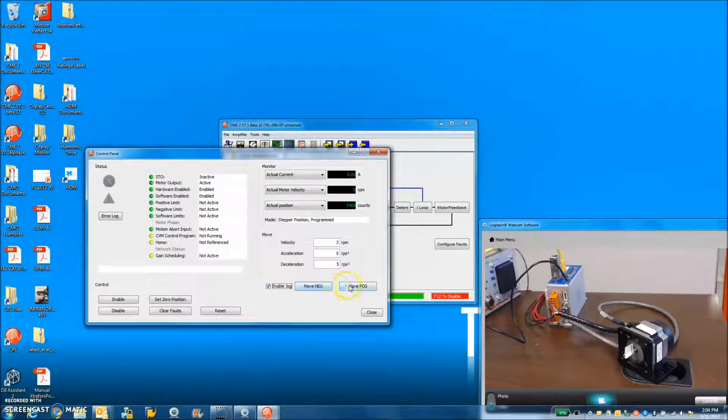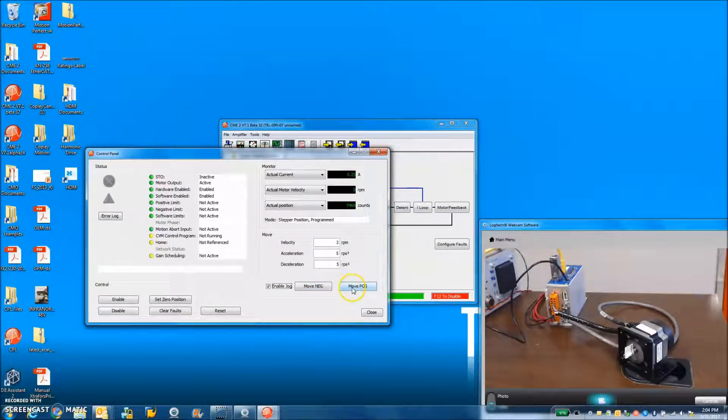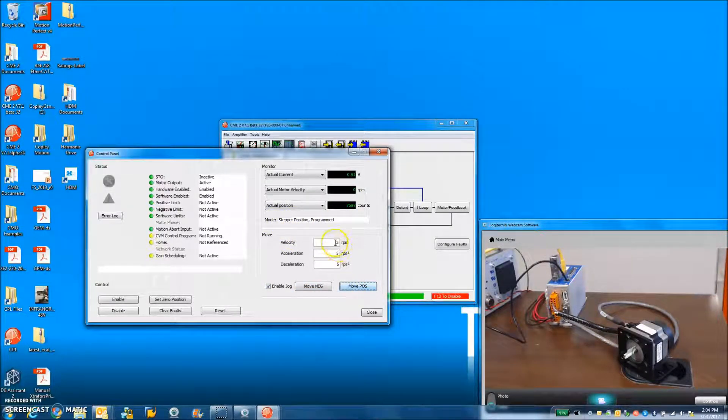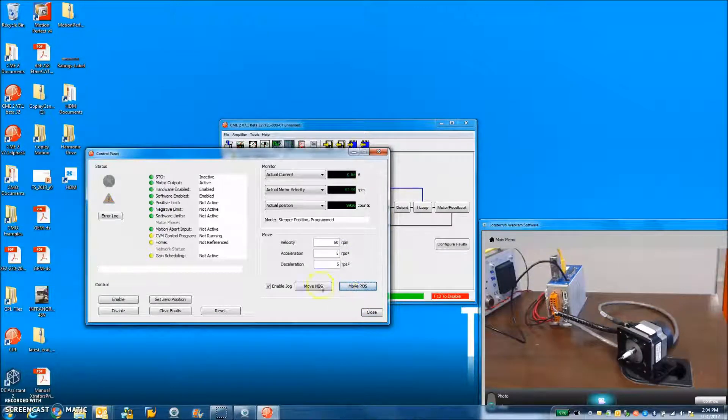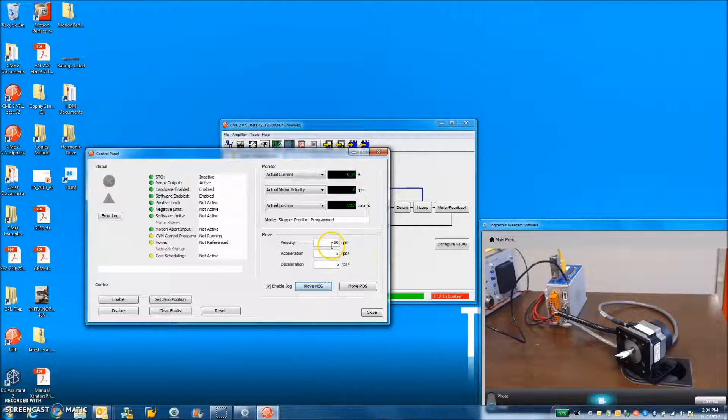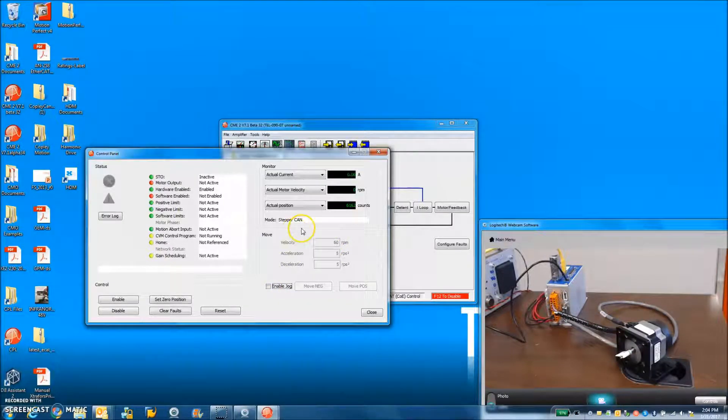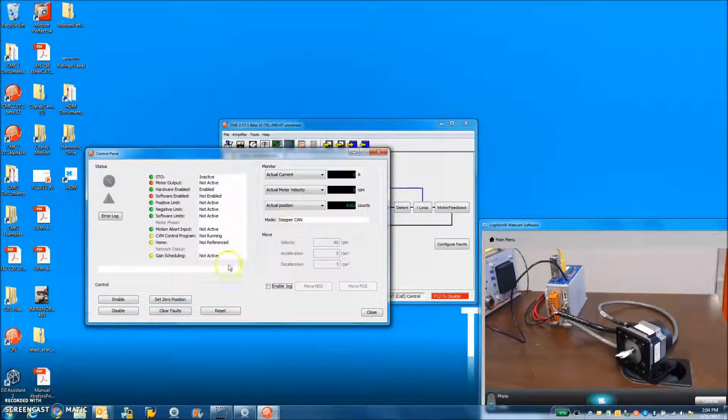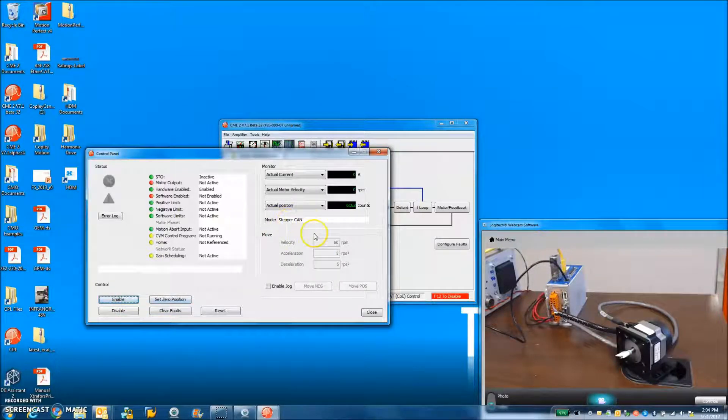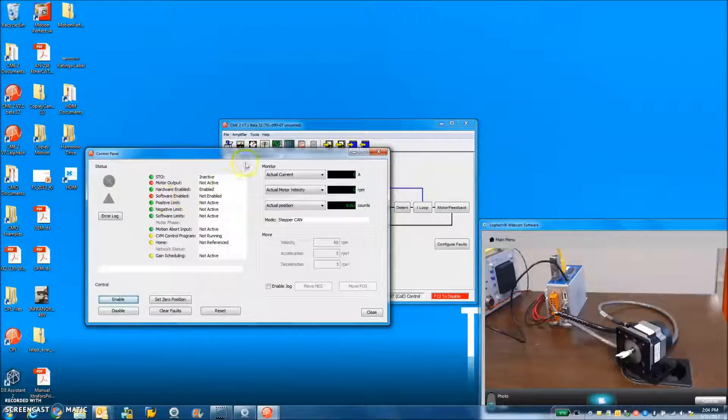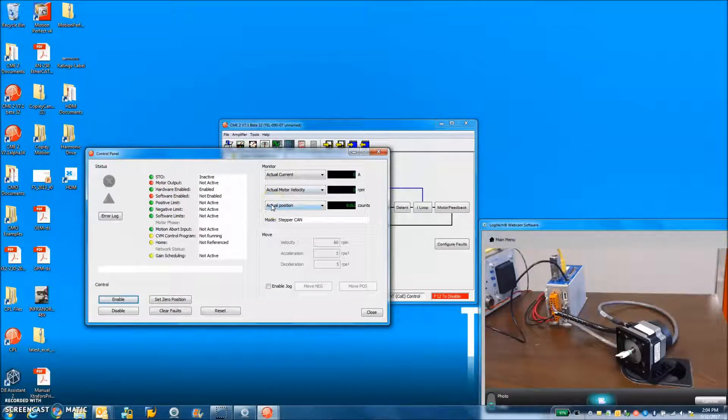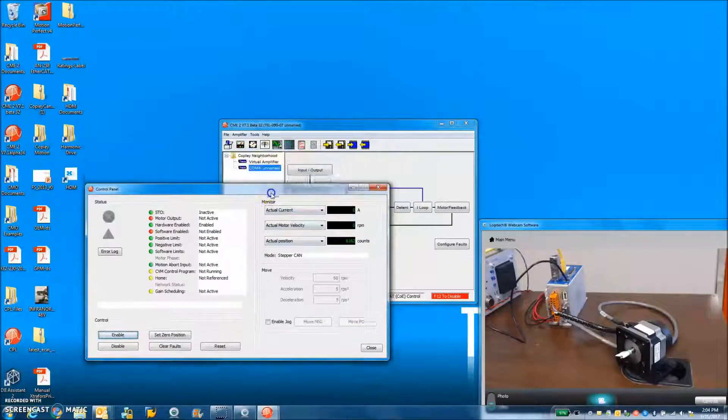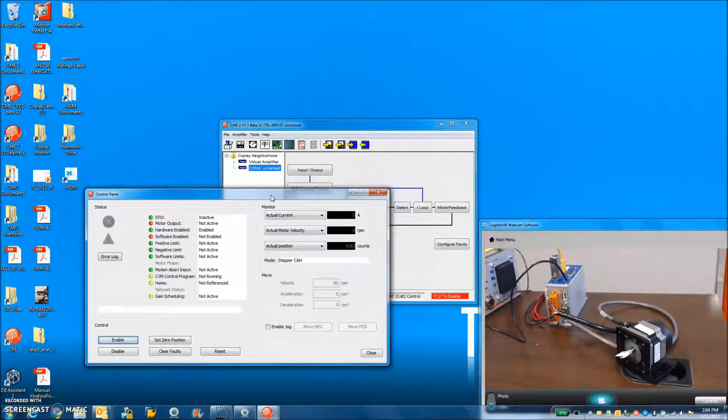If you jog it, notice you're in a position mode, stepper programs. You can jog this thing back and forth. That's pretty cool. When you're done jogging, uncheck the box and make sure it's still in a stepper mode. Disabled mode, stepper mode. When we power up, we're going to be disabled until the EtherCAT master comes in and takes it from pre-operational to operational and then enables the drive. Then we can make some moves.